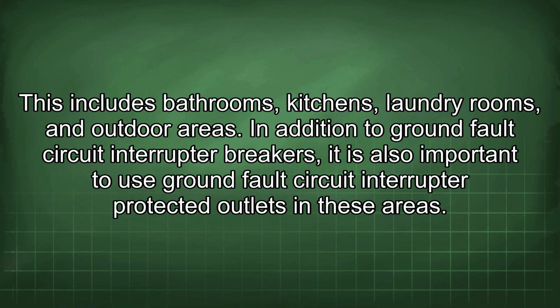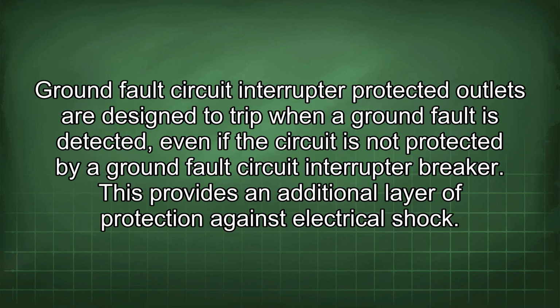In addition to ground fault circuit interrupter breakers, it is also important to use ground fault circuit interrupter protected outlets in these areas. Ground fault circuit interrupter protected outlets are designed to trip when a ground fault is detected, even if the circuit is not protected by a ground fault circuit interrupter breaker. This provides an additional layer of protection against electrical shock.